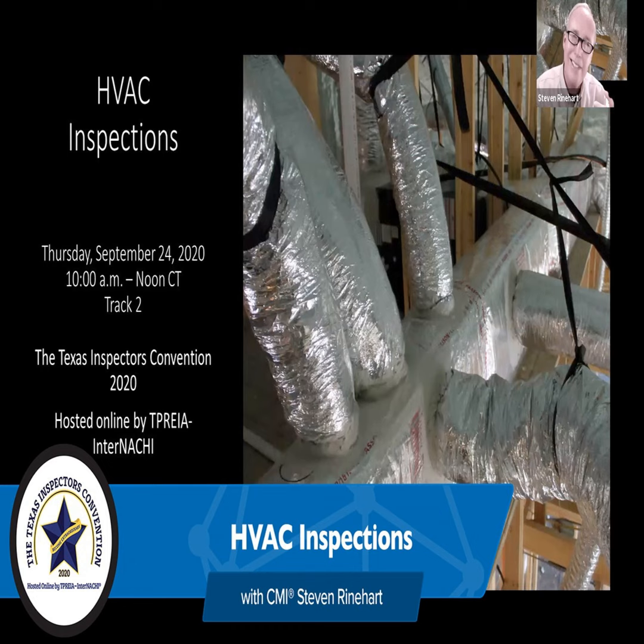Pier and beam house, manufactured home, ducts, plenums in contact with the earth, no brainer. Can't have them laying on the ground. Deficiencies in filters. If I see a filter just plain dirty, I've changed filter. I've opened them up and had a seller looking over the shoulder and didn't know that filter was there. Been there a few years. So deficiencies in the filters, usually sizing, could be just been in there too long, need to be changed.